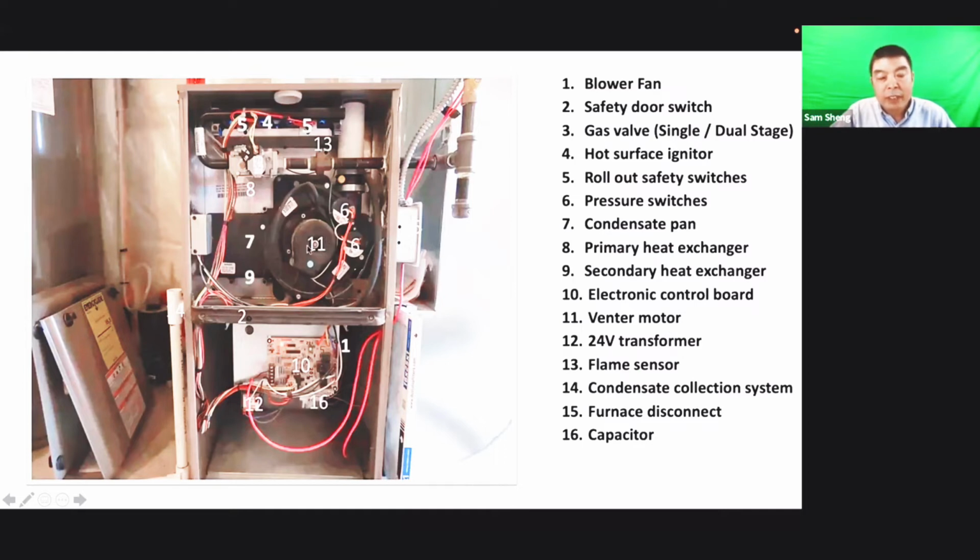Just like this one. This one is easy to make noise. Sometimes the noise comes from the condensate water. If this drain pipe is clogged somewhere, the water will accumulate inside the housing here. If the water goes inside, it cannot come out by itself. So when the inducer motor is running, you will hear water noise inside.